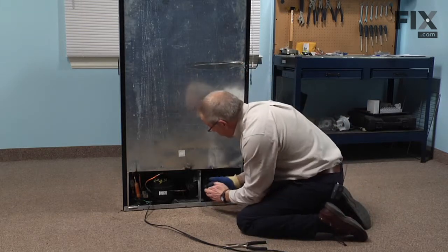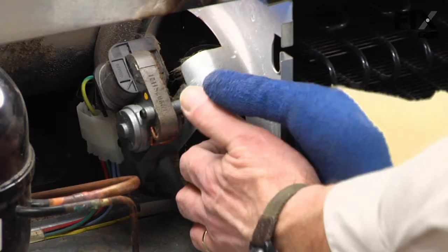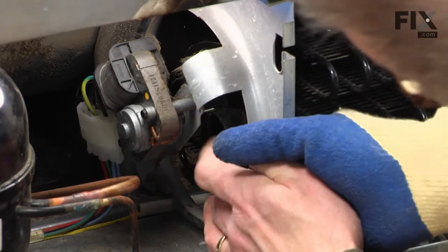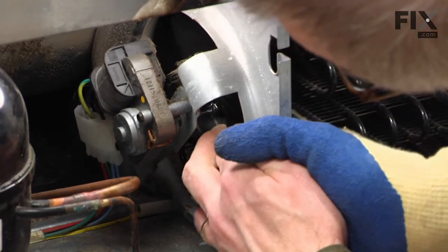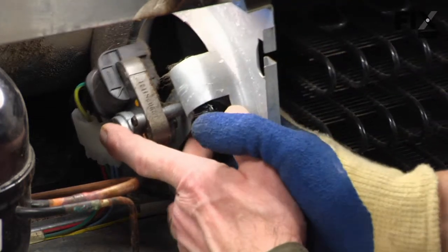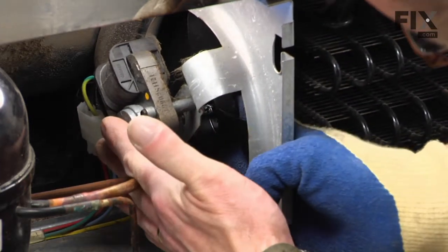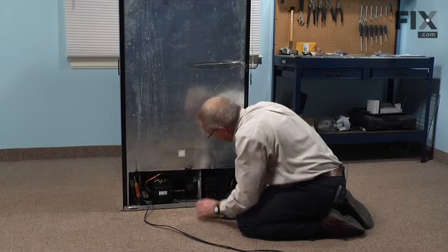With one hand we'll slide the blade in between the mounting bracket and the condenser, line it up with the shaft, and once you have the fan blade centered on the motor shaft simply support the motor, press the blade onto the shaft, and make sure it spins freely and there's no interference with the bracket.